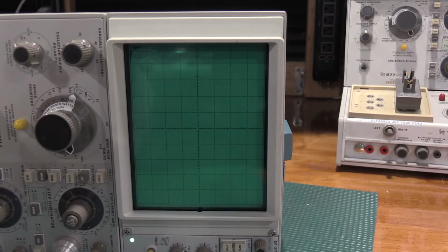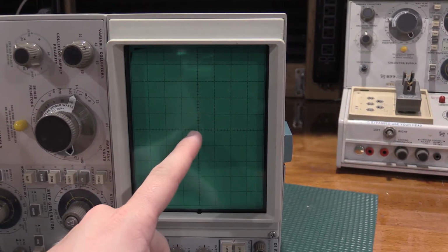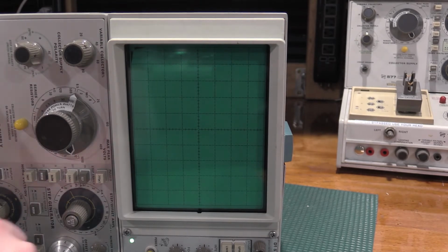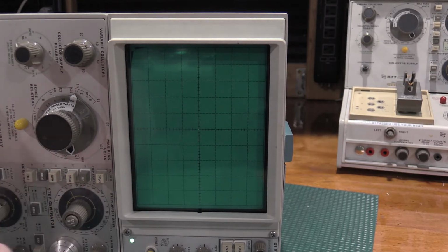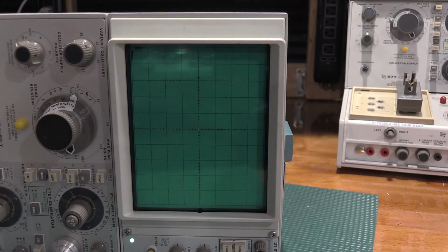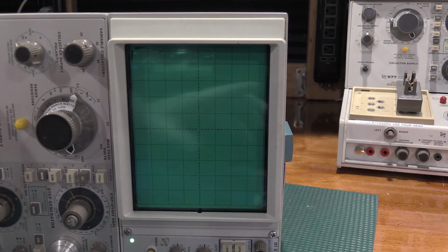Okay, so with the curve tracer on its side, spot is centered, and we want no movement of the spot, or no vertical spot movement for when you switch it between 100 milliamps and 50 milliamps. Obviously we have lots of spot movement, so first adjustment is R610. And you do want to use insulated tuning tools for this adjustment, because there's high voltage all over the bottom of this thing.